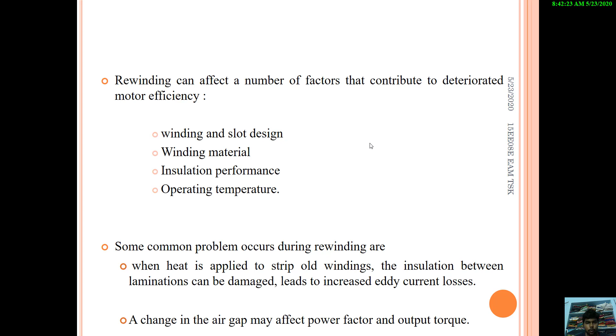In some cases, after rewinding, efficiency can be improved by changing the winding design. After repair or damage, the rewinding design may be changed, and if it is changed, there might be a chance of improvement in efficiency or power factor. However, it is generally recommended that the original design of the motor be preserved during the rewind.